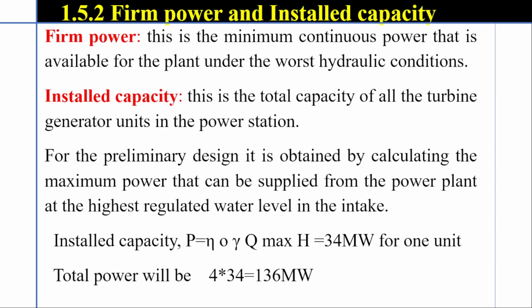Firm power and installed capacity. Firm power is the minimum continuous power that is available for the plant under the most critical hydraulic conditions. Installed capacity is the total capacity of all the turbine generator units in the power station. For the preliminary design, it is obtained by calculating the maximum power that can be supplied from the power plant at the highest regulated water level in the intake. Installed capacity is calculated by using this formula.